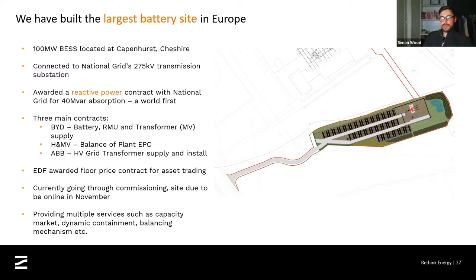Where we are with the site at the moment is we've built it. We're currently going through our commissioning process, and we're hoping to have wrapped that up within the next few weeks, with the site entering full operations towards the end of this month. This site will not only provide the reactive power service, which is the most unique part of this asset, but it will provide the typical services that any other battery system would also do, such as dynamic containment, which is a frequency response market, balancing mechanism, capacity market, and so on.